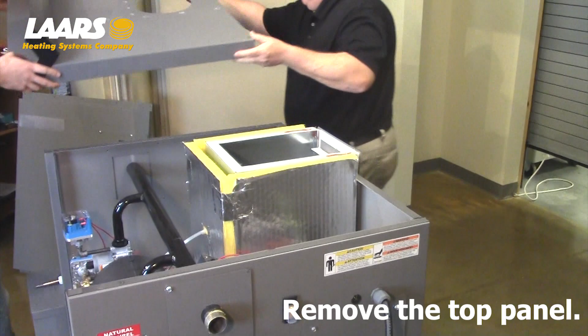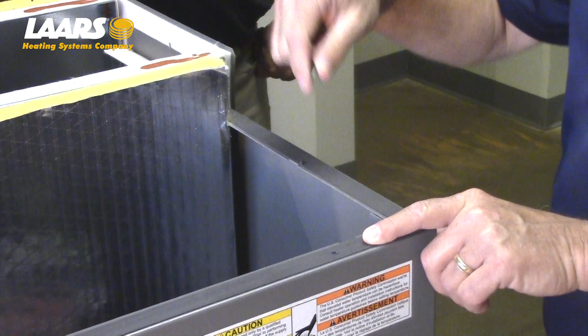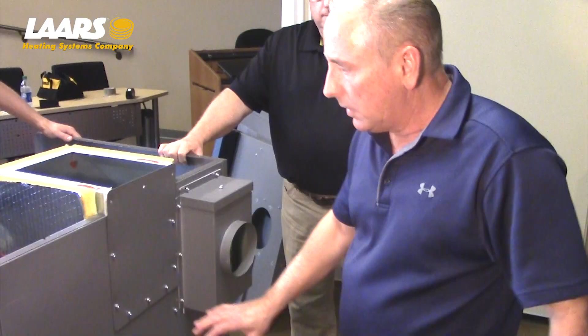Along the sides and the back there may be clips holding the top jacket to the side panels. You will have to reach in from the inside, take these out of position, as well as remove the screws, to lift the panel off. Next, we're going to take the back jacket off the boiler.